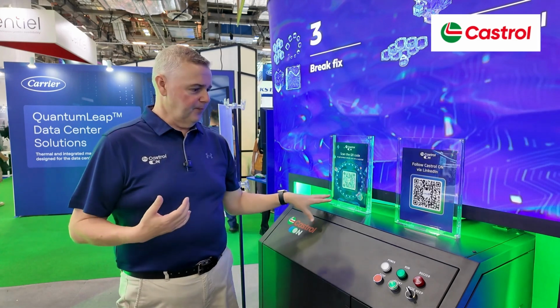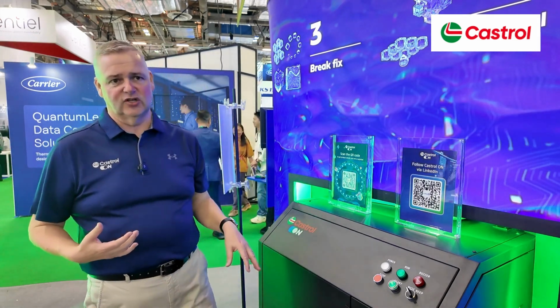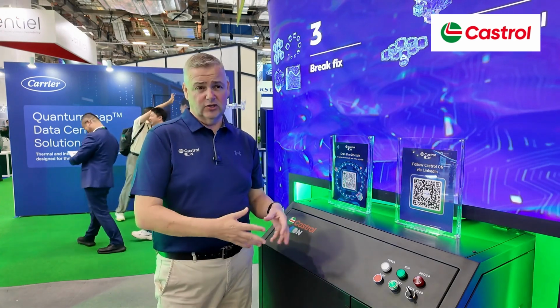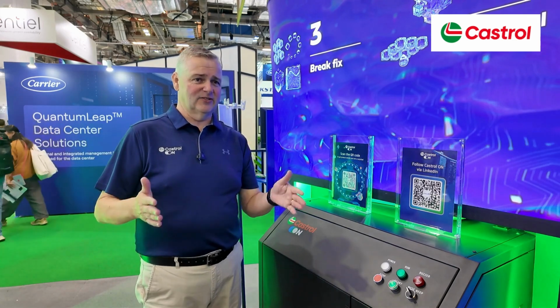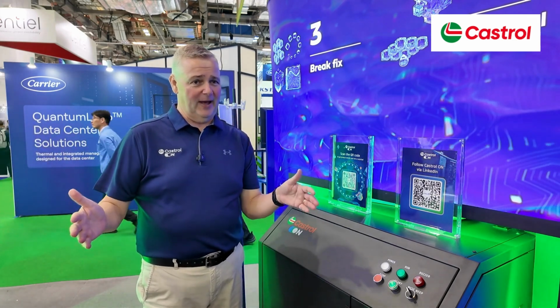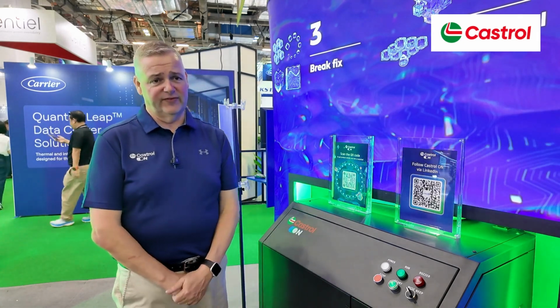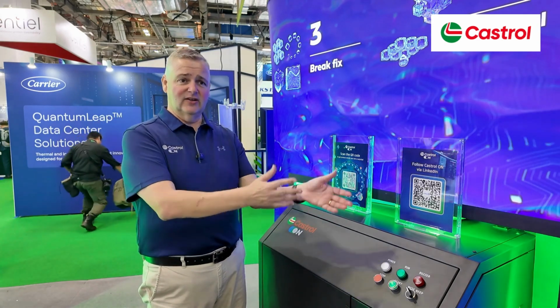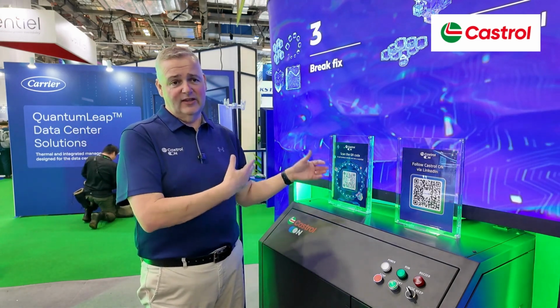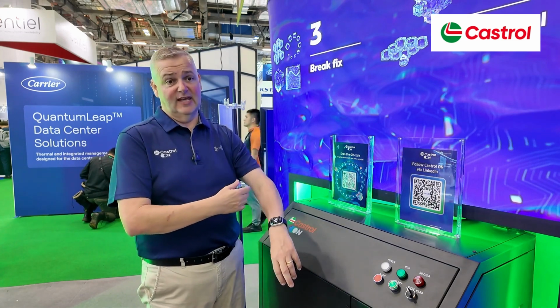The first product fits into installation and commissioning, but also maintenance. Moving around a lot of fluid in a big 1,000-litre tub with a pallet jack or in a drum isn't really great in the white space of a data centre. So we've found a way with the liquid refill cart to do that safely, decanting outside of the space, moving the fluid in, and then decanting it either into a rack manifold or directly into the secondary fluid network.